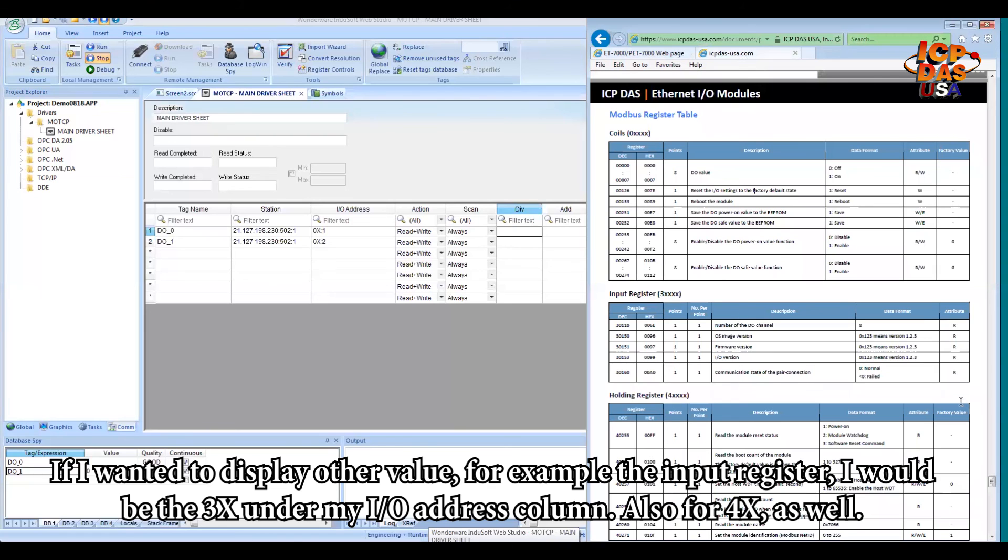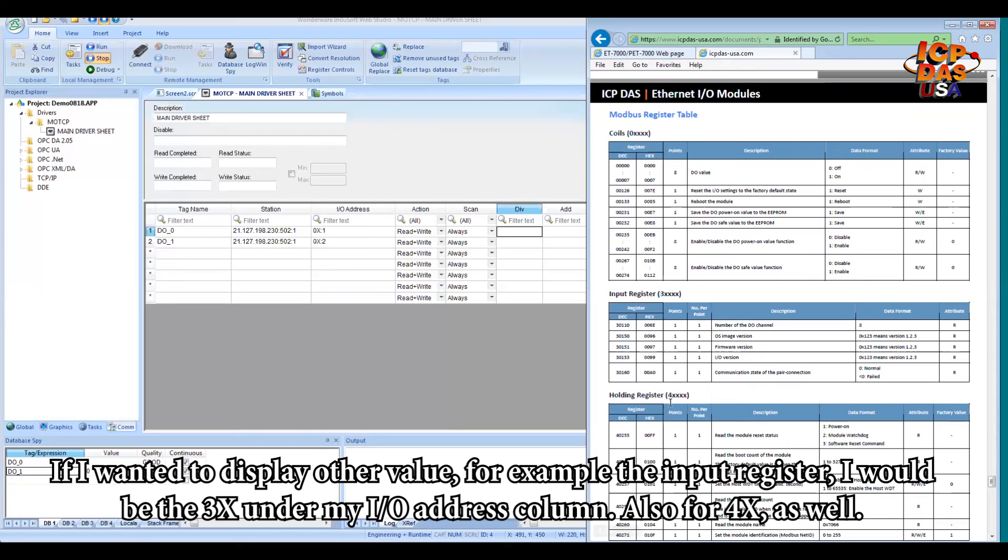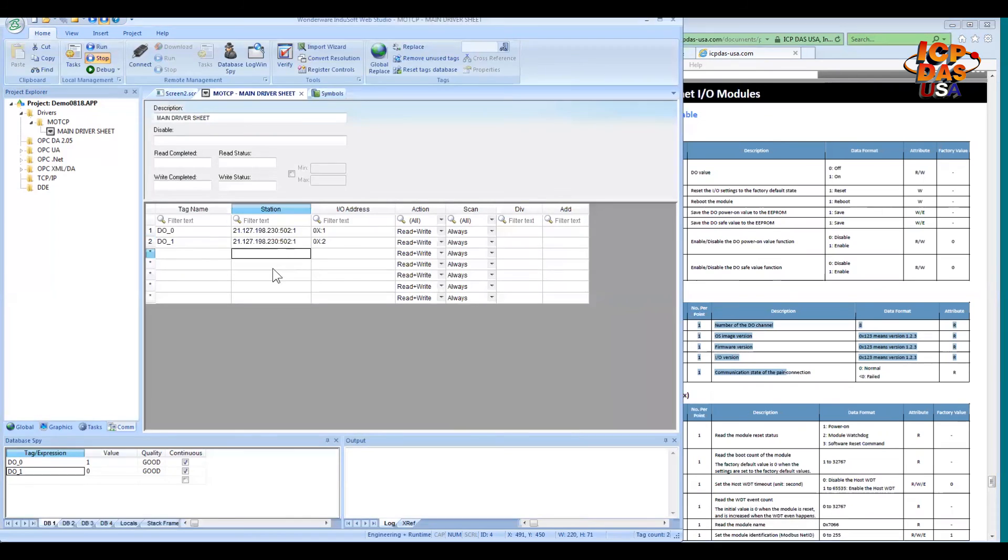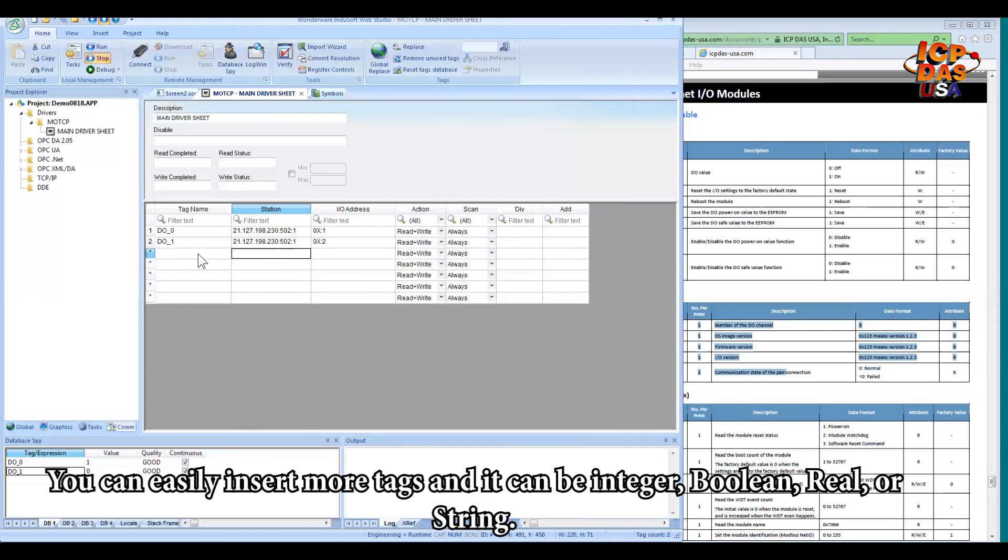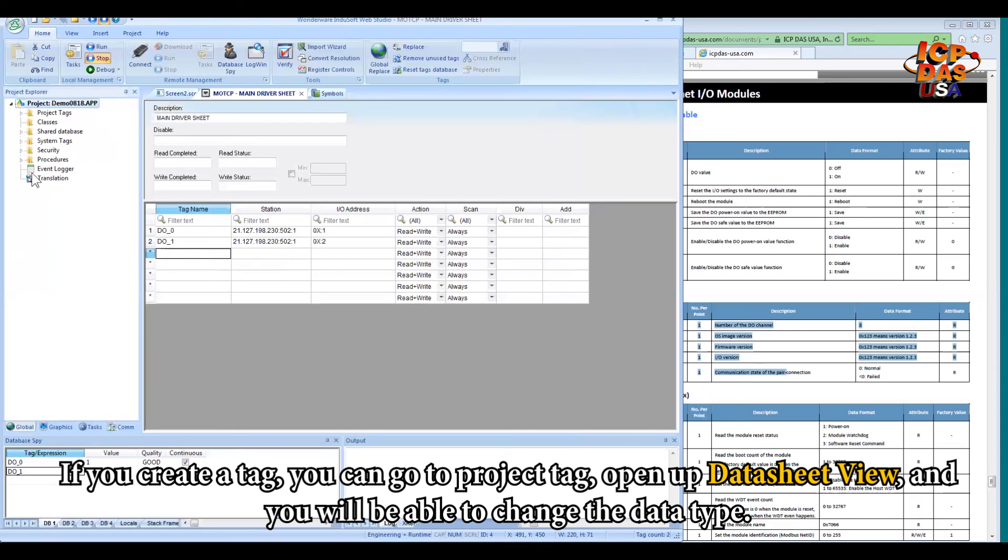So if I want to display other value, for example, the input register, I will put the 3x under my I/O address column. So also for 4x as well. So 3x, 4x, depending on what kind of register you want to display or create in InduSoft. So you can easily insert more tags. And it could be integer, boolean, real, or string.